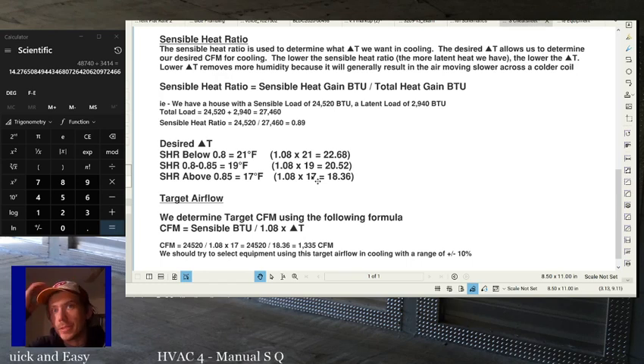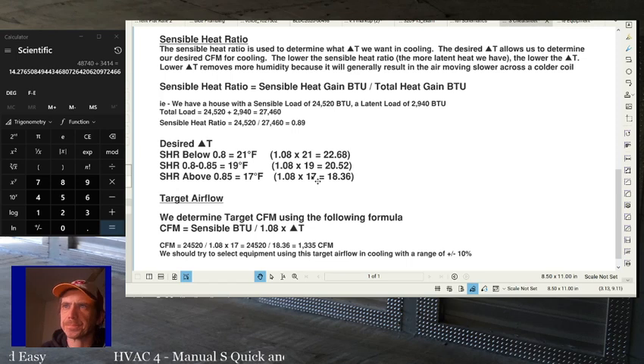Well, we do that by determining the sensible heat ratio. The sensible heat ratio gives us an idea of how much of the load is sensible and how much of the load is latent. So that makes a big difference, because the more latent heat we have, the lower we want the airspeed to be so that we can remove more humidity. Remember, latent load in the case of cooling is basically just humidity load. All right? So, to determine how much CFM we actually want, we have to determine that sensible heat ratio, take that into account, and use some rules that Manual S gives us to determine what we want our delta T to be. And once we know what we want our delta T to be, we can use that to calculate how many CFM we need.